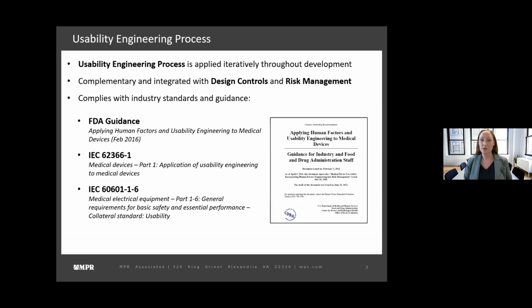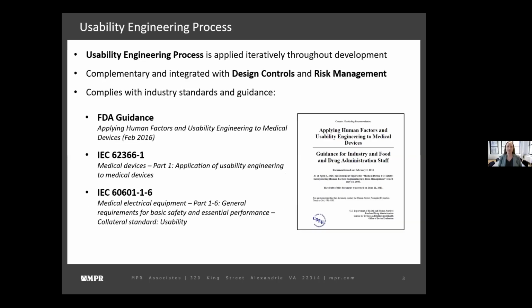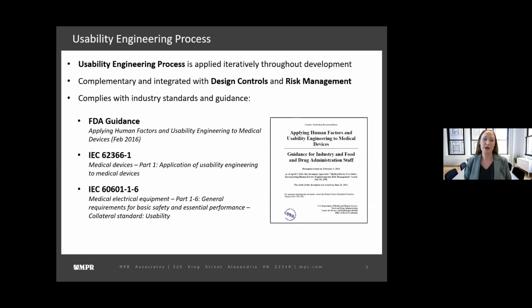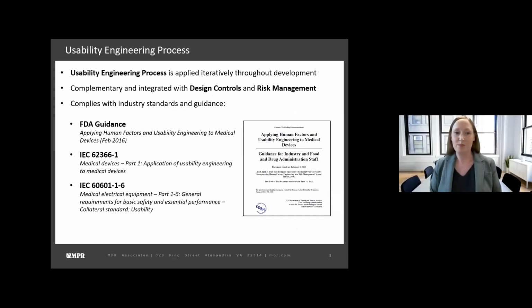The main standard that defines the usability engineering process is IEC 62366 Part 1. That defines the elements of the usability engineering process and is complementary to FDA guidance, which provides additional guidance on applying human factors and usability engineering to medical devices. So those are really the top two standards or guidance that are used in application of the usability engineering process, although there's a lot of other guidance out there that is also helpful. And I'll mention also just briefly the IEC 60601 Part 6 collateral standard on usability. That really just creates a bridge between the 60601 series for basic safety and essential performance of medical electrical equipment. It's essentially a pointer or bridge for how you can use IEC 62366 to comply with those medical electrical requirements.